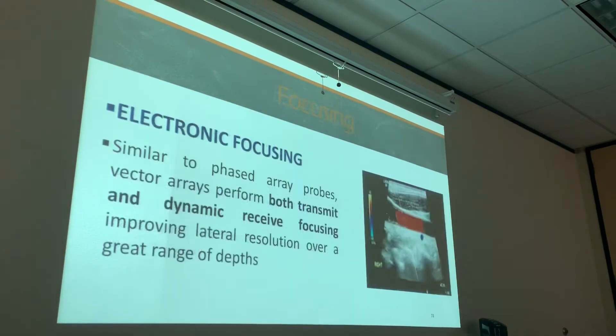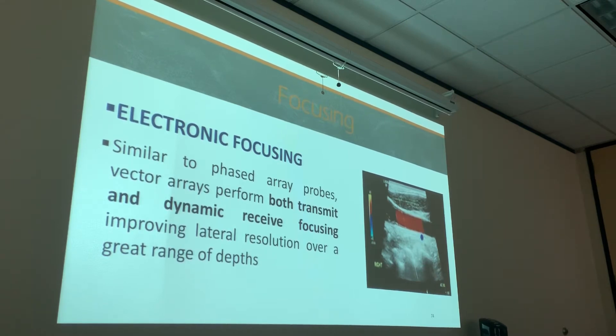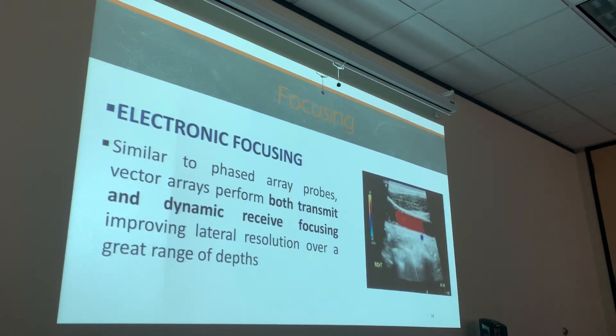So again, some but not all the crystal elements are fired simultaneously. Little groups of elements are excited at one time to create this beam — that's how it's like a linear sequential array. The beam radiates in all directions like a linear phased array, giving us the trapezoidal image. Focusing is electronic. Similar to phased array probes, vector array probes perform both transmit and dynamic receive focusing, improving lateral resolution over a greater range of depths.